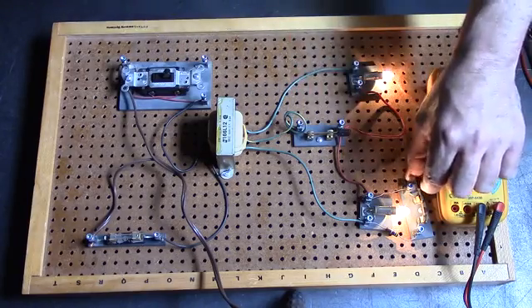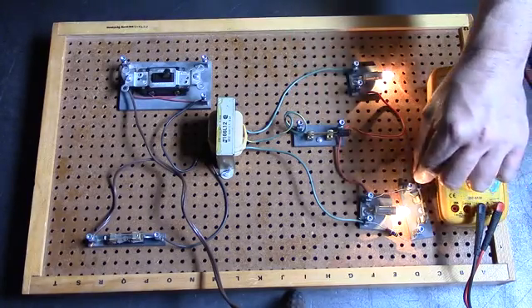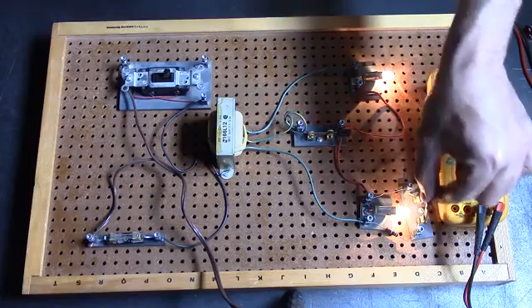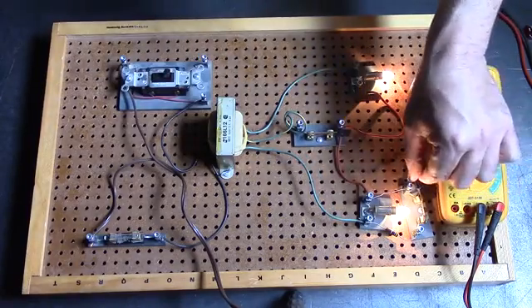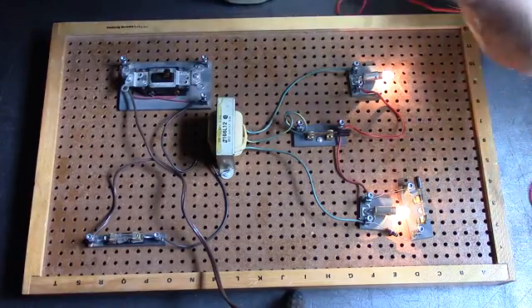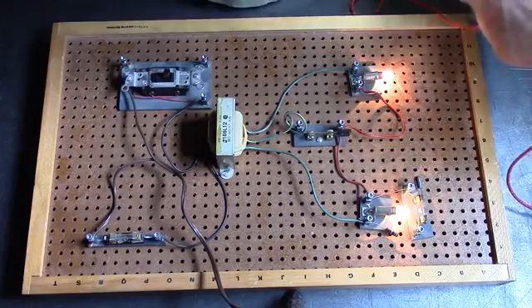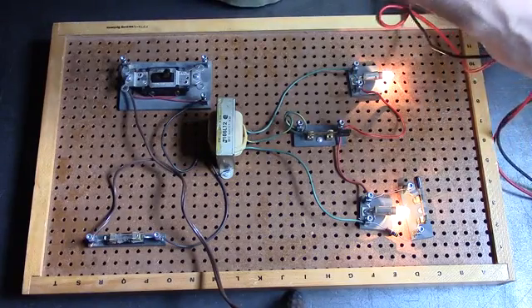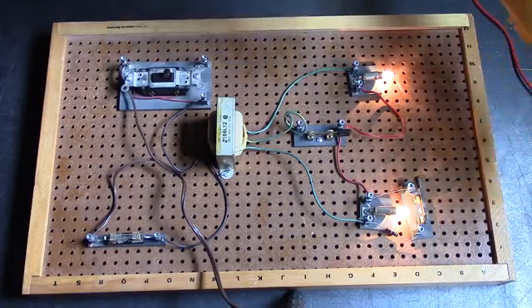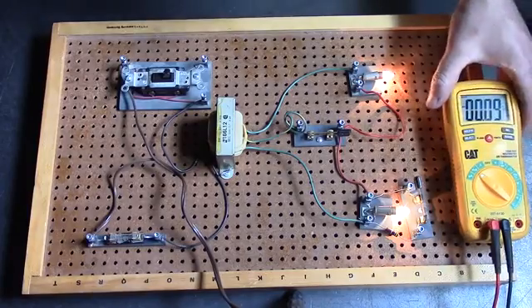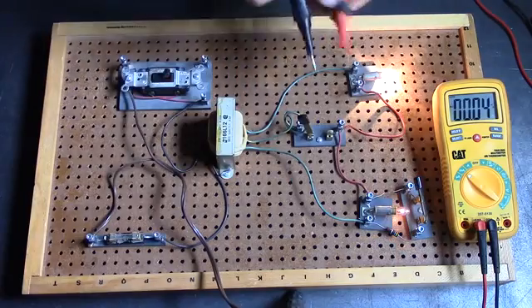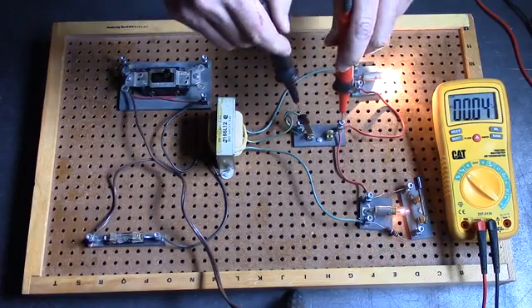So I guess the question needs to be answered is how much current is ever flowing across that neutral conductor. Obviously the current is going to be changing as I balance or unbalance the loads. So what I'm going to do is move my multimeter over to the milliamp scale and we'll actually measure the current flowing across the neutral. Go into milliamps, stay on auto ranging AC.